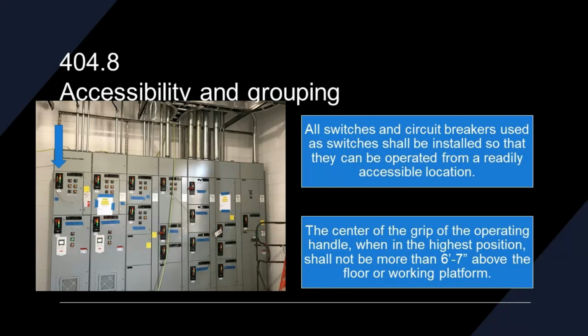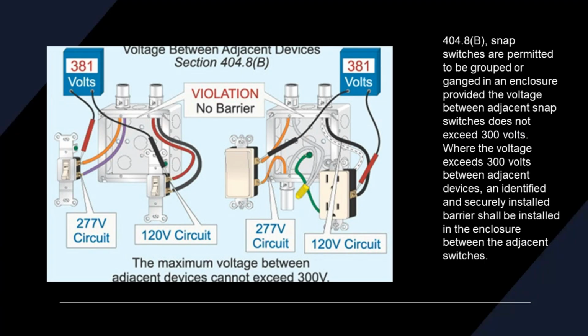404.8 tells us about accessibility and grouping. All switches and circuit breakers used as switches shall be installed so they can be operated from a readily accessible location. This is a big one. The center of the grip of the operating handle when in the highest position shall not be more than 6'7" above the floor or working platform. All right, anytime that you have over 300 volts between circuits, if you have, in this instance, a 277 volt circuit out of one transformer and 120 out of the other, you are required to have a barrier when you exceed 300 volts between adjacent devices. So if you exceed 300 volts, you're to put a barrier in these boxes.